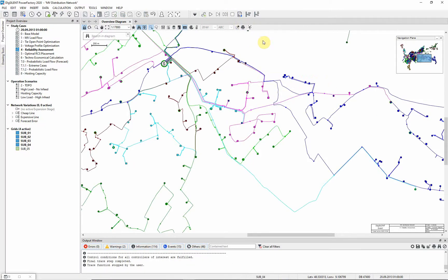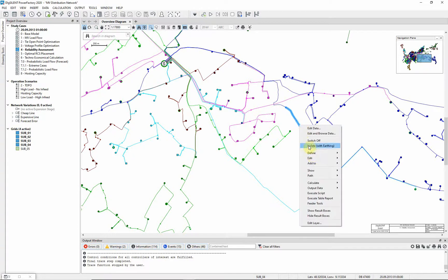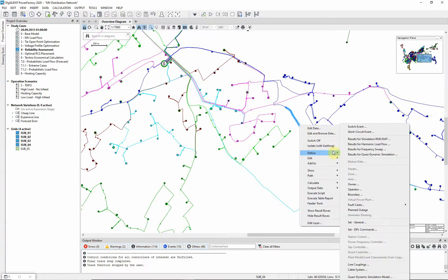Now we will carry out the reliability calculation for the entire network. First we will specify a planned maintenance on one of the lines. We will choose this line, line 1224. Right-click on the line and select Define Planned Outage.